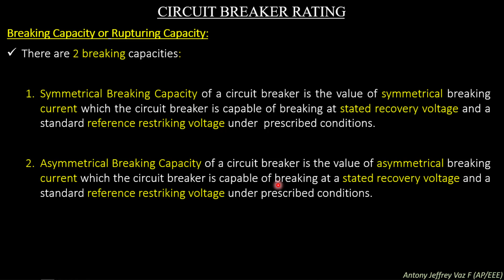Similarly, the asymmetrical breaking capacity of a circuit breaker is the value of asymmetrical breaking current which the circuit breaker is capable of breaking at a stated recovery voltage and standard reference restriking voltage under prescribed conditions. During this asymmetrical breaking, the natural power wave and the short circuit current wave will not match. They will have asymmetrical characteristics, and this is due to the presence of both DC and AC components mixing together, as we see in the above formula: square root of (X divided by root 2) whole squared plus Y squared. So the mixing of AC and DC components causes the asymmetrical breaking capacity.